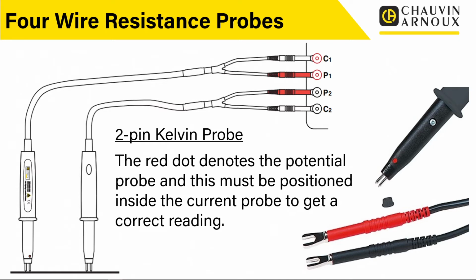But one thing to note really carefully is that on these ones of ours you've got a little red dot, and that red dot indicates the voltage connection, the potential connection. So the outside one, the one that hasn't got the dot, is the current connection, and the one that's got the dot is the potential connection. As you can see on the left hand side there, when we're connecting these probes up, we turn the red dots onto the inside. So your potential connection is on the inside, your current connection is on the outside. That's how we achieve the correct positioning of these probes. So you can see where it is, you can position it when you're carrying out your measurements, and that ensures that you get the best and most accurate measurements by using these probes.